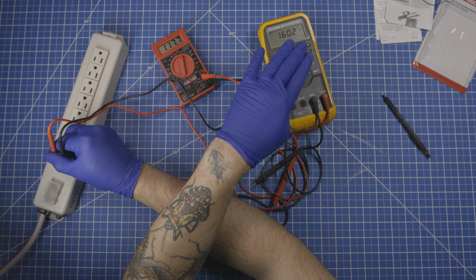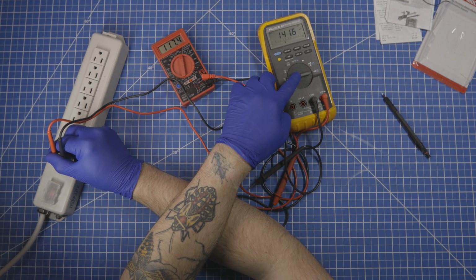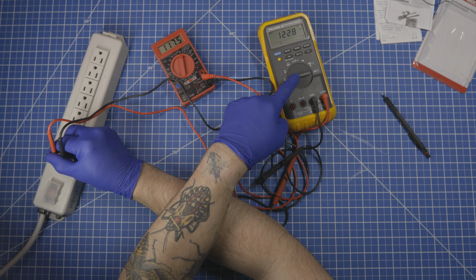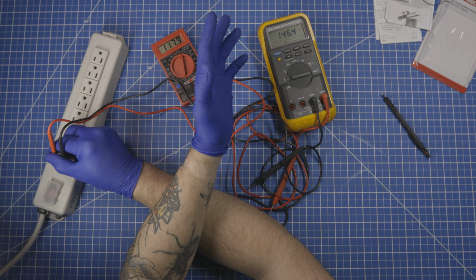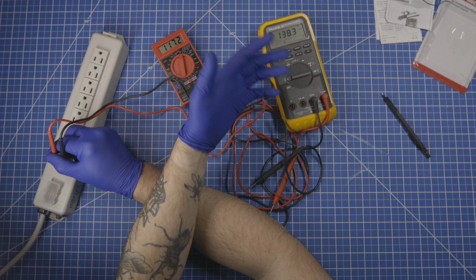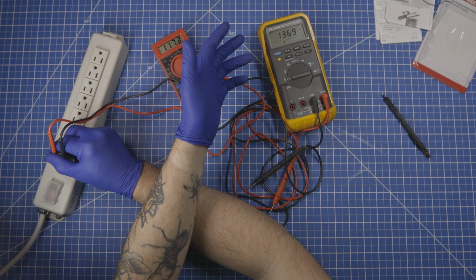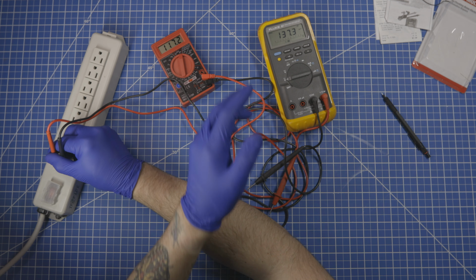That said, we can't be positive this is right. Now, this is a calibrated Fluke 87, but it could have fallen out of calibration since its last calibration. We would want to verify that if we were going down that road of fussy precision.